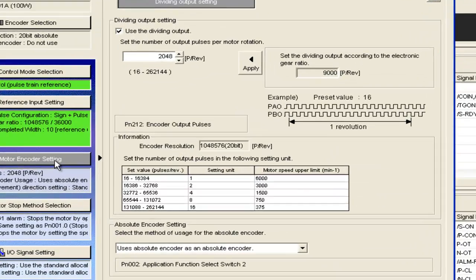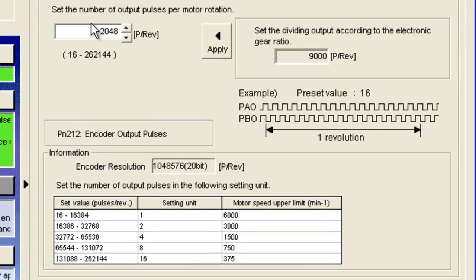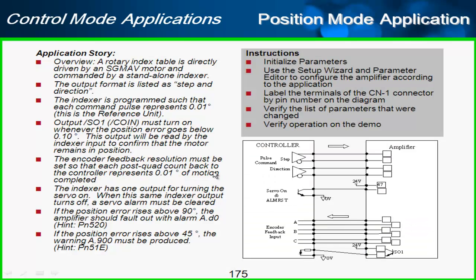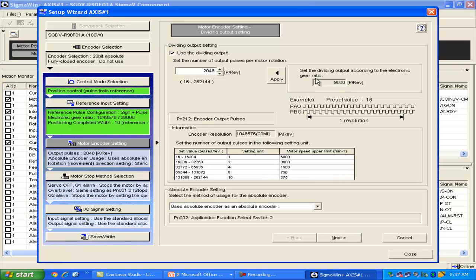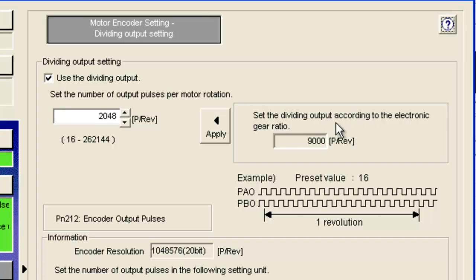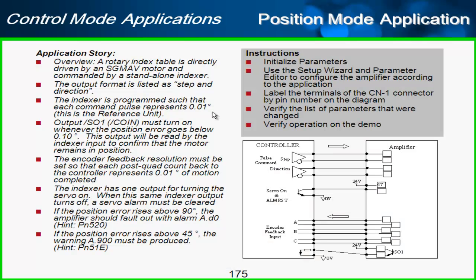Moving on to the motor encoder setting. We are able to set the number of pulses per motor rotation. And here I've said that the encoder feedback resolution must be set so that each post-quad count back to the controller represents 0.01 degree of motion completed. This is actually what's happening here, where it says set the dividing output according to electronic gear ratio. Why 9,000? Well, 9,000 is pre-quad pulses. So after quad, that would be 36,000. Basically, you can see that if the reference unit is 0.01 degrees, then 360 degrees equals 36,000 reference units.